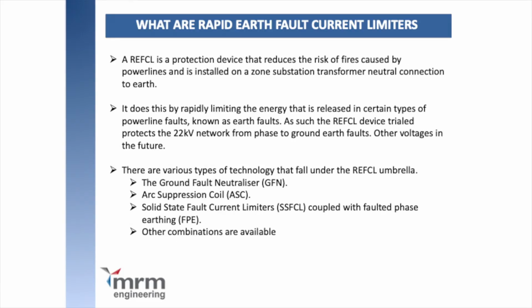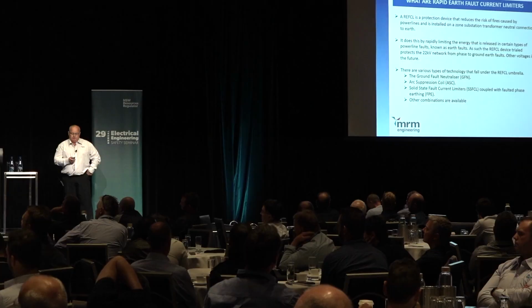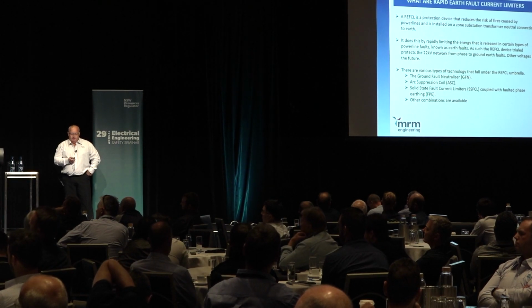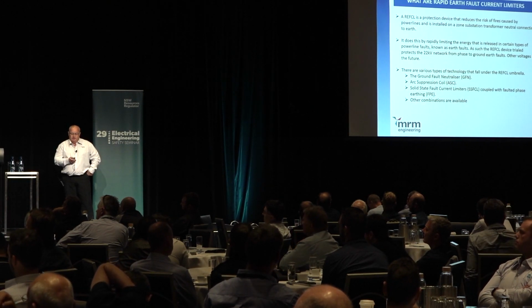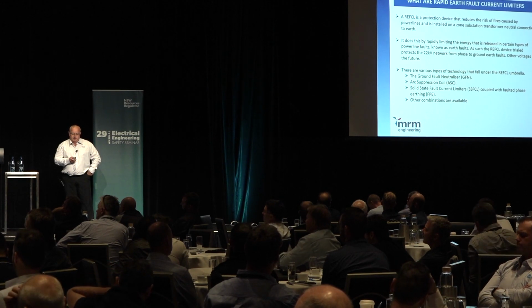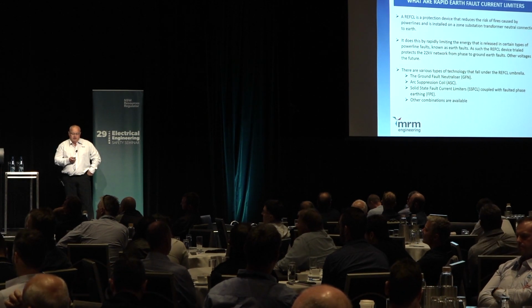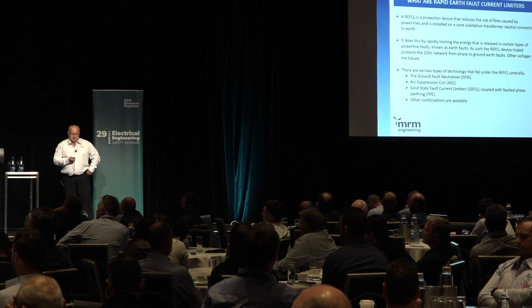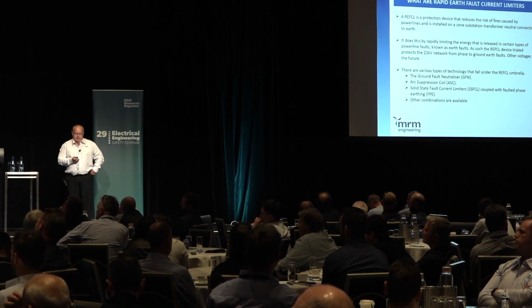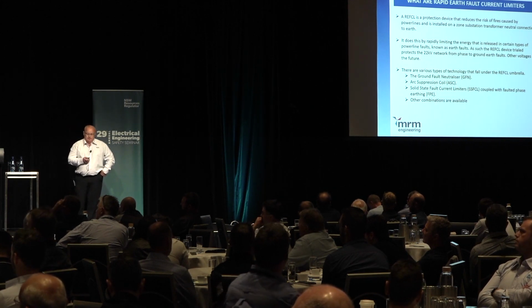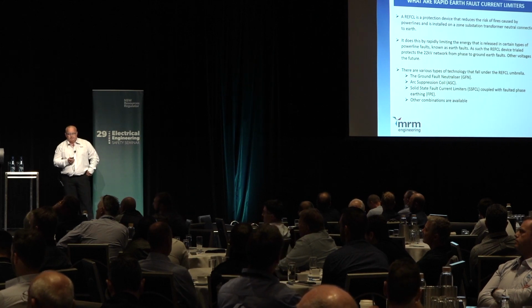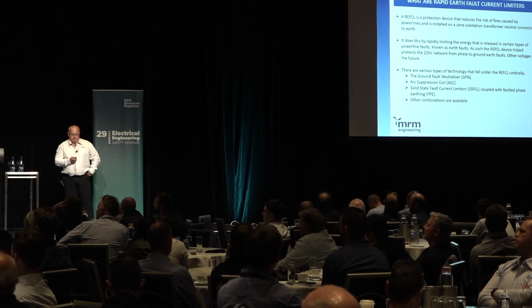Just a bit of background. A rapid earth fault current limiter is a device which reduces the risk of fires caused by power lines, installed in substations between the transformer and neutral connection, rapidly limiting the energy that is released by a certain type of power line fault known as earth faults. The REFCL device is trialled on the 22 kV network, and they're looking at other voltages in the future, but that's probably 5 to 10 years away while they sort out the 22 kV stuff they're actually working on now.